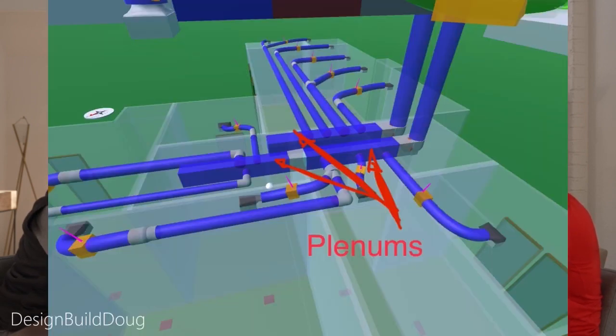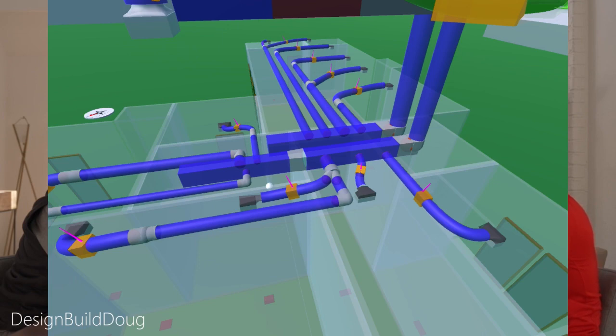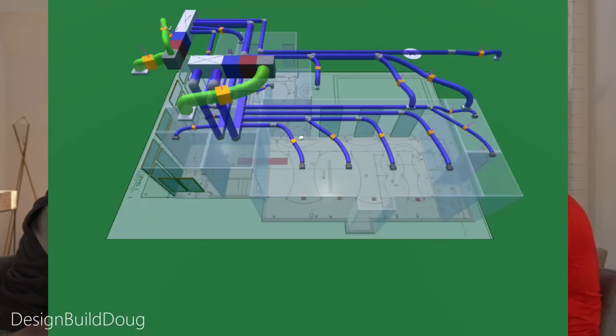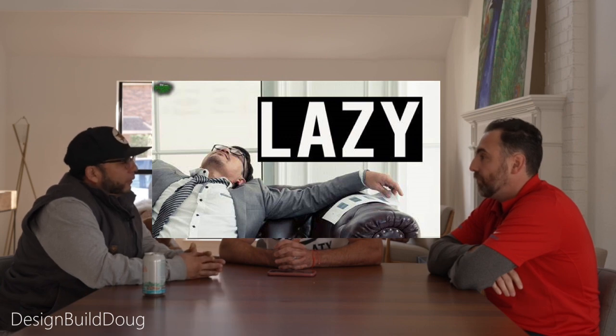The idea of a plenum is this box is supposed to pressurize, and then airflow goes down each duct consistently. If you were to put ducts on the end of this plenum, there would be no pressurization, and all the airflow would go down the end of that duct run. You want all duct runs to have an equal chance at getting airflow, determined by the dampers or duct sizing on the plenum. Airflow is lazy and dumb, so we have to control it with pressurization and simple measures like dampers.